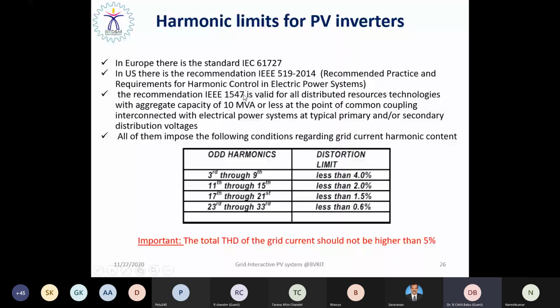But the IEEE standards are meant for the steady state, and the IEC standards cover both steady state as well as transient. Most widely, IEC standards are used for industrial purposes, and for renewable energy sources, where the steady state response is okay, we follow the IEEE standard, right?